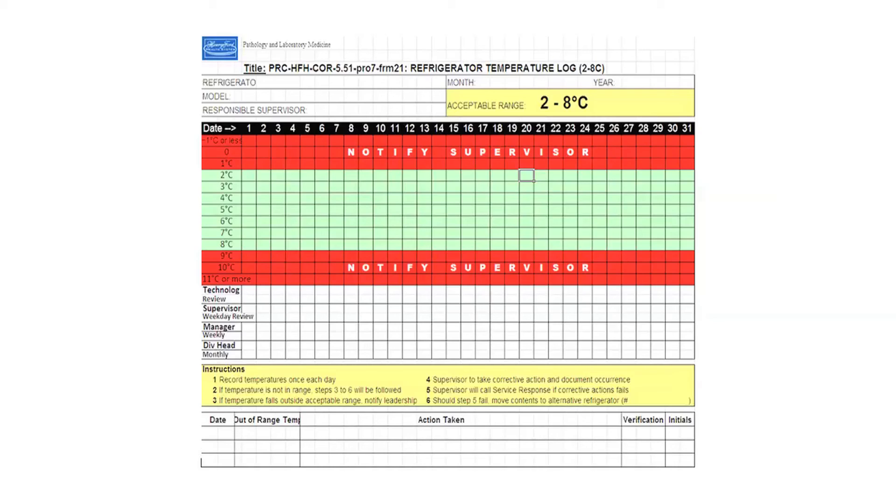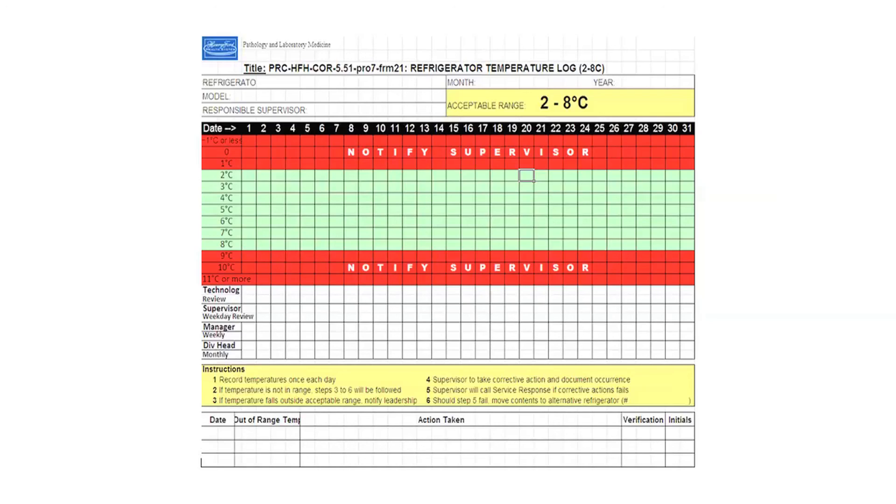And finally, if you see at the bottom, we actually have a table which says date, out-of-range temperature, action taken, and initials. If I was looking for root causes or trends, I have all the information on one page. I can find the temperature, I can find if it's in range or out of range, and I can find if it was out of range, what was done about it. Everything in one piece of paper.